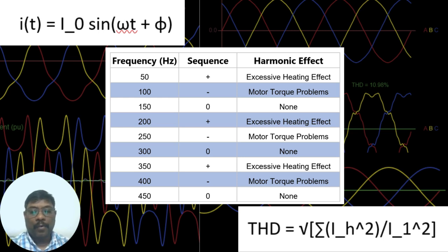The third harmonic, 150 hertz, is a zero sequence present in the neutral circuits. The fourth harmonic, 200 hertz, can produce excessive heating because it's a positive sequence effect.